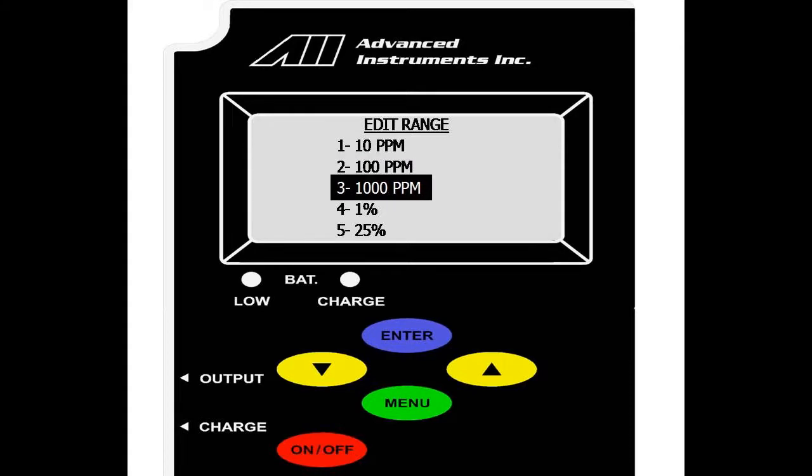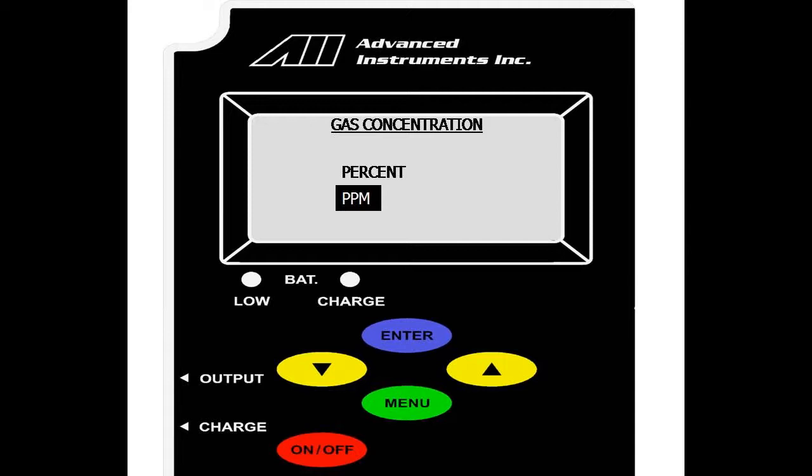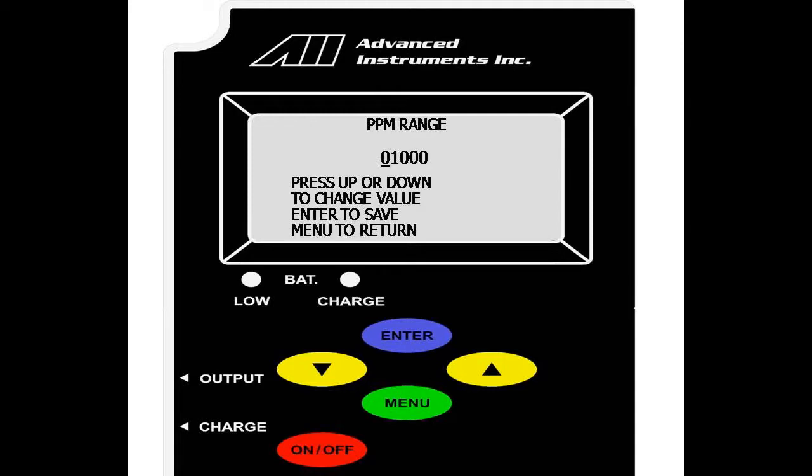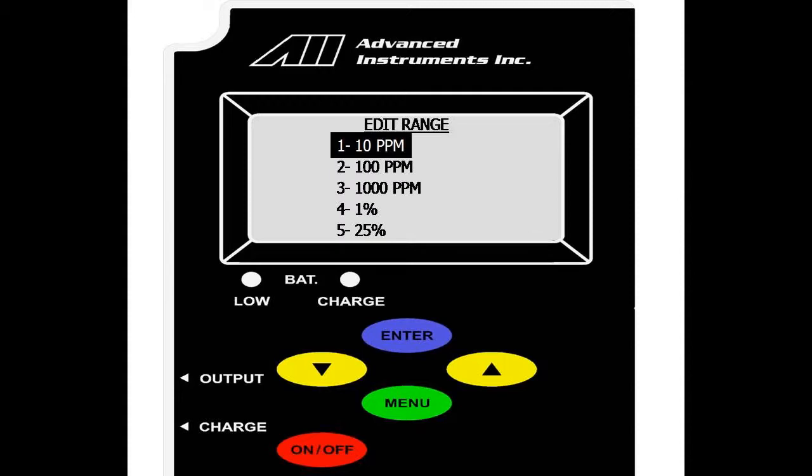We select enter on 1000. We will change it to a parts per million value. And again, up or down to change the value. Enter to scroll over. This option allows all five user ranges to be changed.